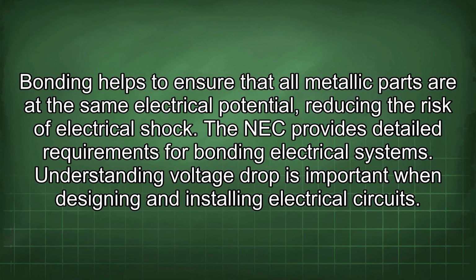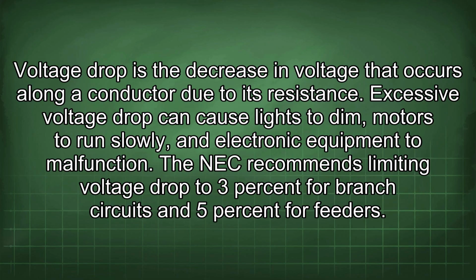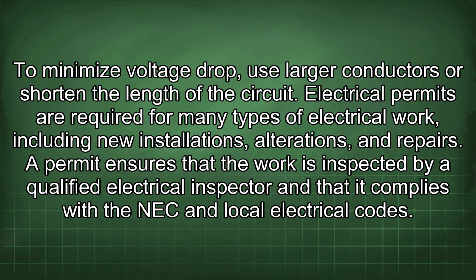Understanding voltage drop is important when designing and installing electrical circuits. Voltage drop is the decrease in voltage that occurs along a conductor due to its resistance. Excessive voltage drop can cause lights to dim, motors to run slowly, and electronic equipment to malfunction. The NEC recommends limiting voltage drop to 3% for branch circuits and 5% for feeders. To minimize voltage drop, use larger conductors or shorten the length of the circuit.